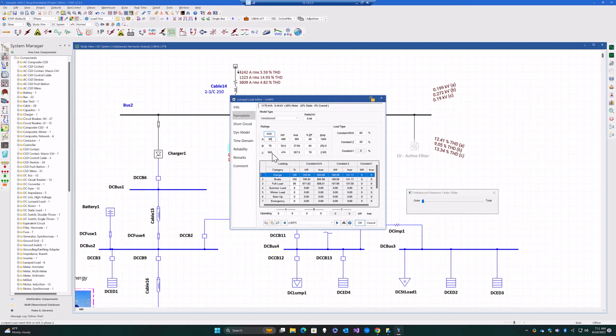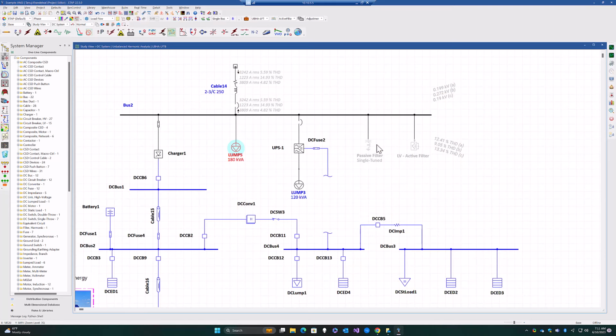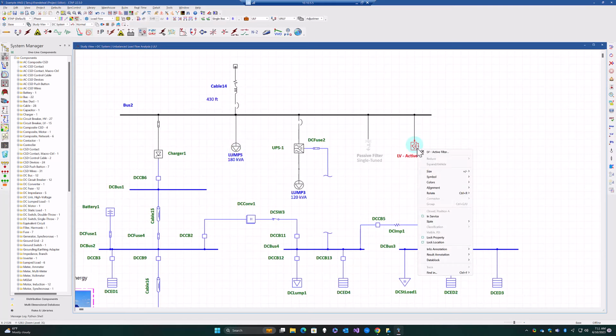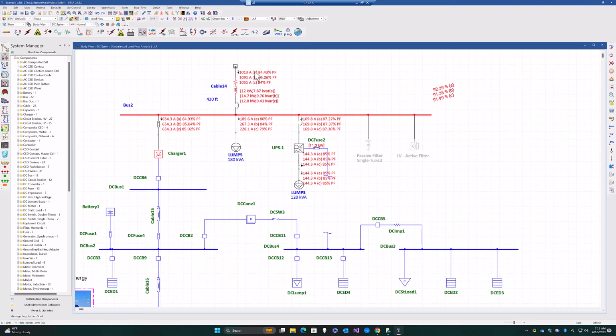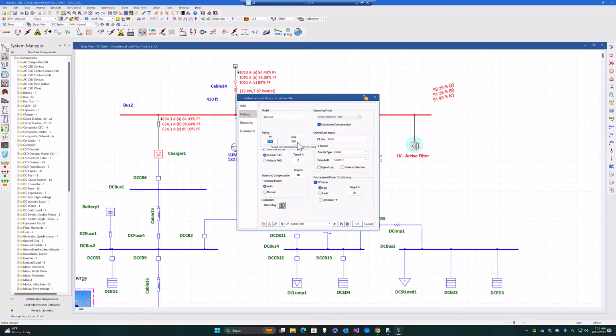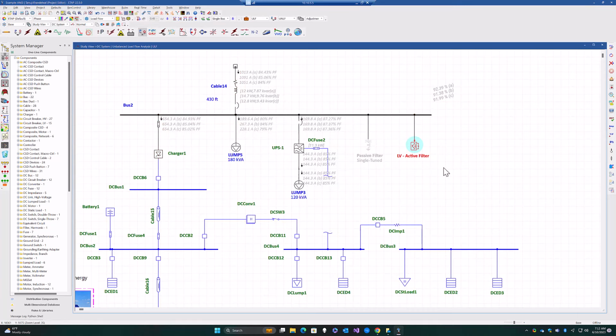So let's make this a bit of a reasonable unbalanced load on a low voltage system, about 180 kVA of unbalanced load. And we want to, of course, switch over to our unbalanced load flow mode. Let's run unbalanced load flow first so we can see that we have around 85% power factor. We have a little bit of unbalance in our current. Let's take this particular active filter and set our power factor target of 90%, and run our simulation again.